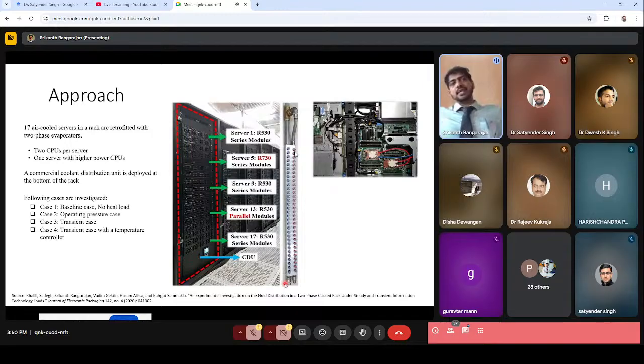The next thing we wanted to do is take the same cold plate and test it in a data center, in more of a rack-level approach. So for this, we chose a rack in our own data center, and we replaced the 17 air-cooled servers in a rack and retrofitted them with two-phase evaporators. We had 2 CPUs per server and 1 server with very high power CPUs, and we replaced all of the air-cooled heat sinks with liquid-cooled cold plates.